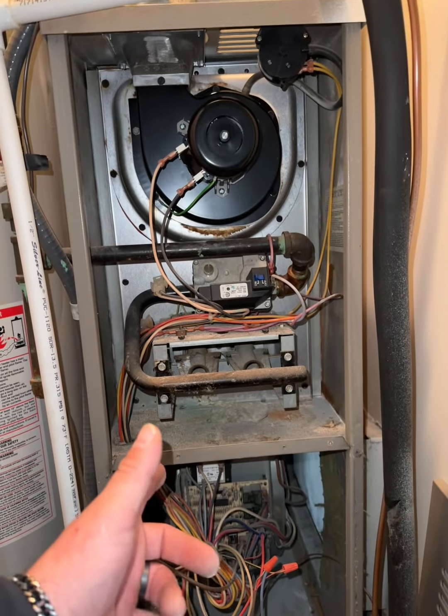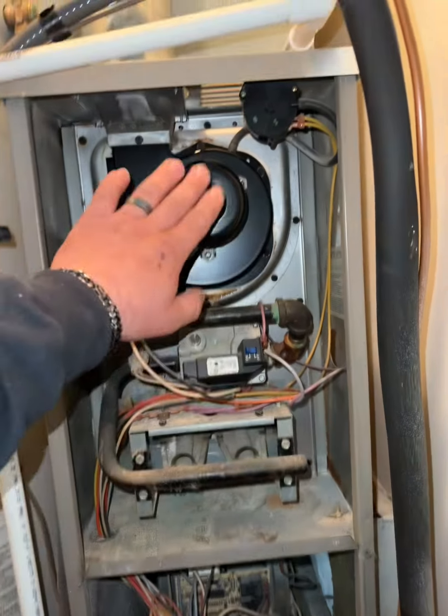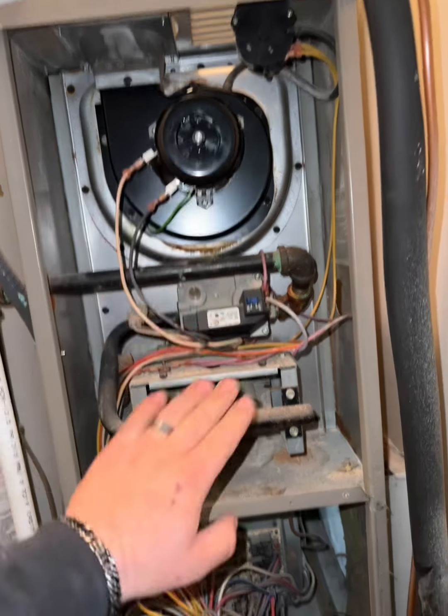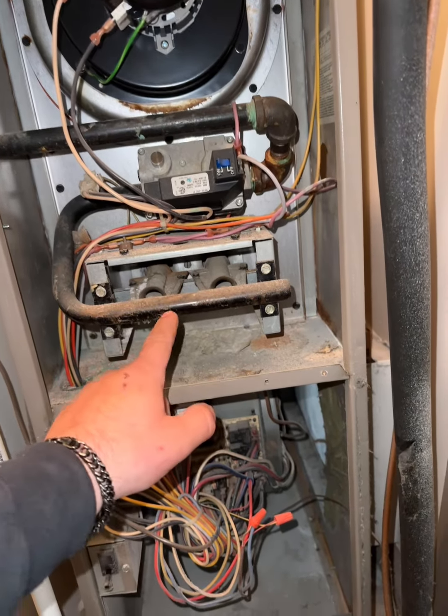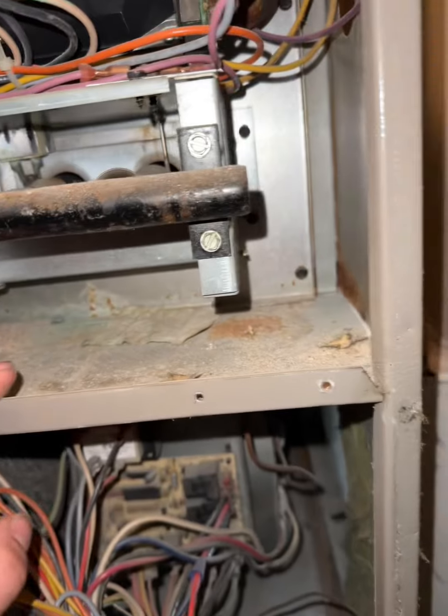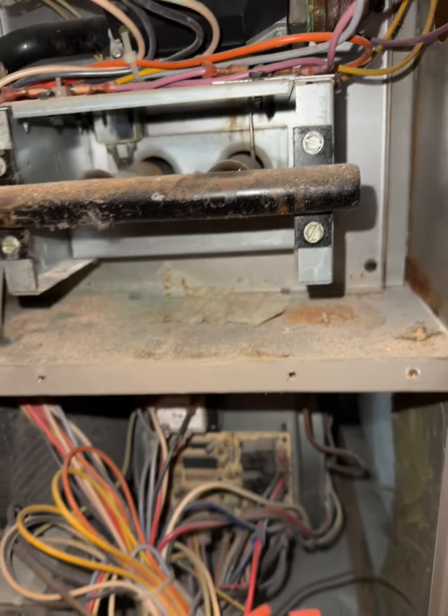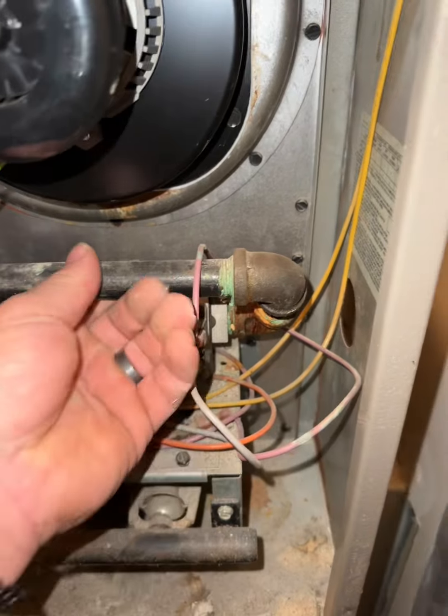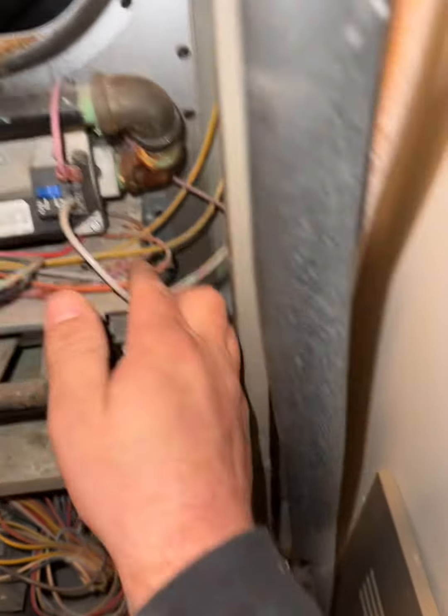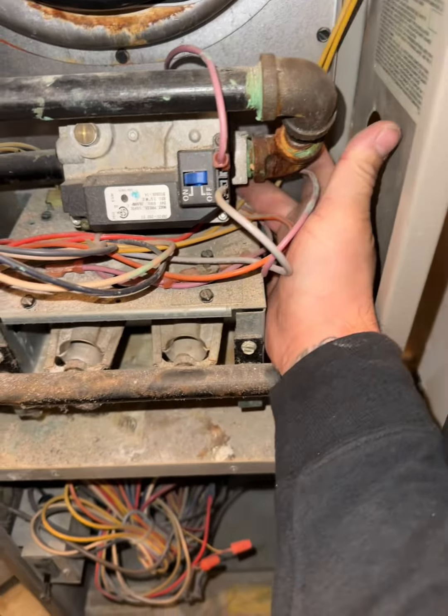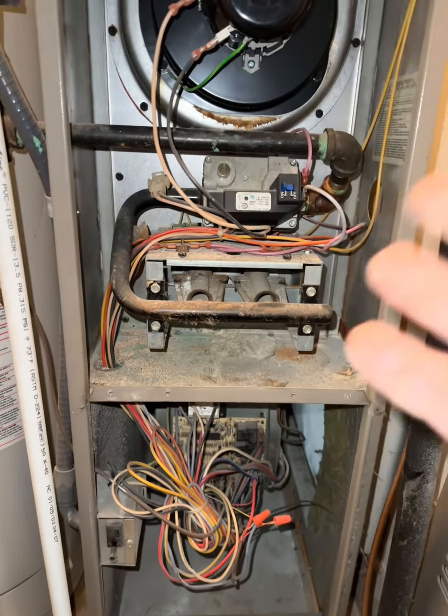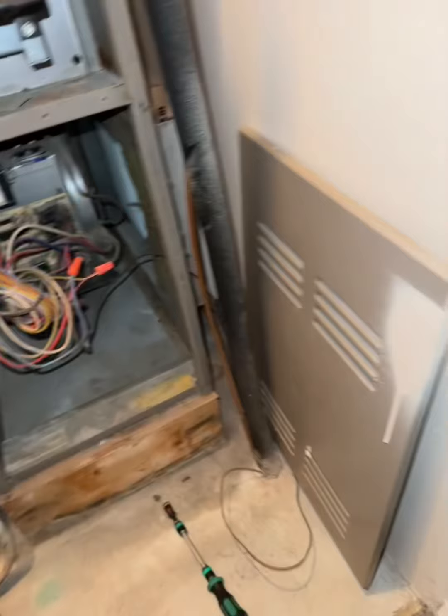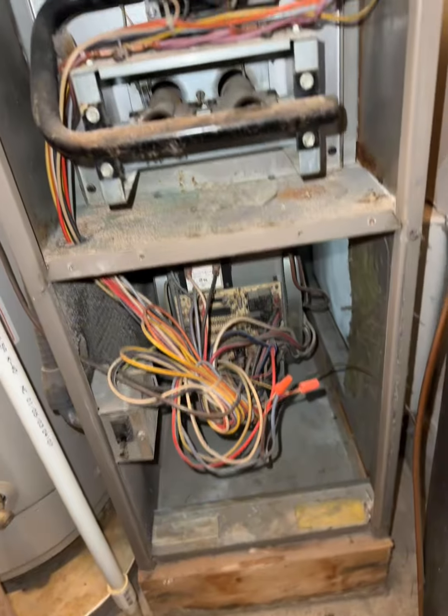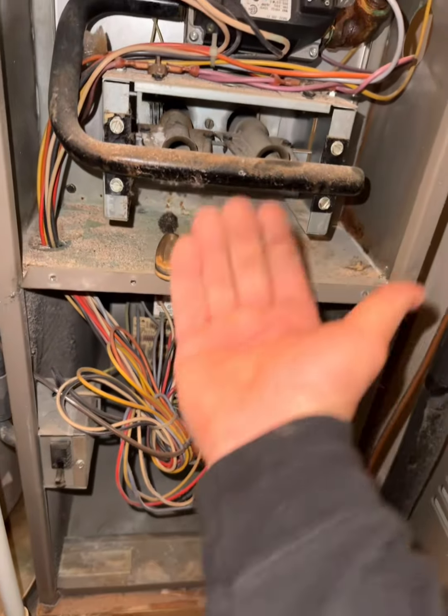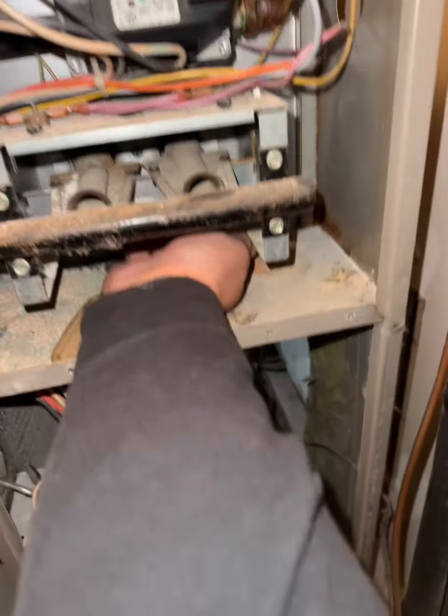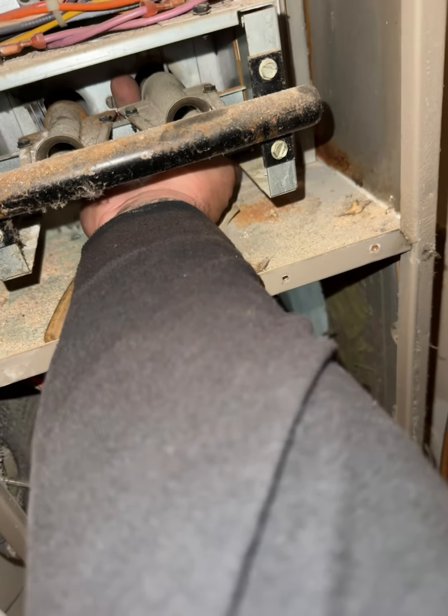All right, so we got a Goodman furnace here. What maintenance has already done is they have changed the inducer motor. Flames will come on for a short second and shut right off. So I'm suspecting a dirty flame sensor, which is back there. And as you can see how Goodman has installed their unit, that flame sensor is nearly impossible to get without really mangling this up. Let me show you a quicker way. What we're gonna do is get it from underneath and just kind of cup action. Get it right in there. You see my fingers?